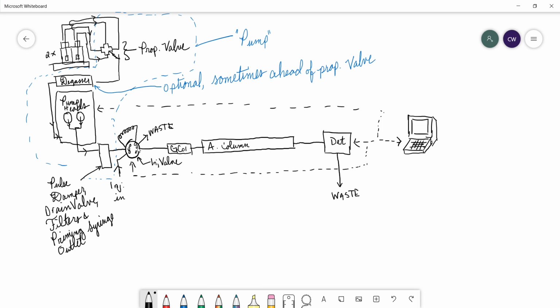Okay, and then there will also be an outlet to the column system. So that is 2 inputs, 2 outputs, and 2 lines for the injection valve. So at minimum, there are 6 openings in an injection valve. Okay, and at any one time, 3 of them are connected together. All right.